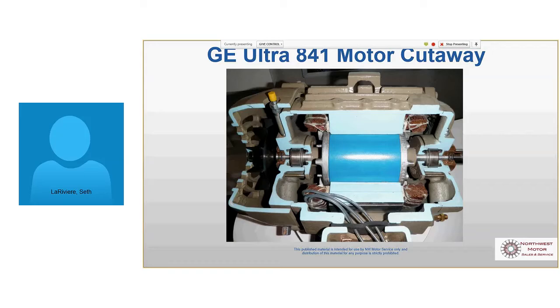Inpro seals, front and back. Inpro seals are designed to keep contaminants out of motors. You see it here. You can hit these with a 90 psi pressure gun. Won't get water inside the bearing. They're not washdown motors. They do make washdown rated motors that are designed to be hosed down continually. They'll run submerged practically for a little while. These are mostly just designed to keep moisture and contaminants out of the bearings. And then the lifting lugs, this is kind of a neat feature.